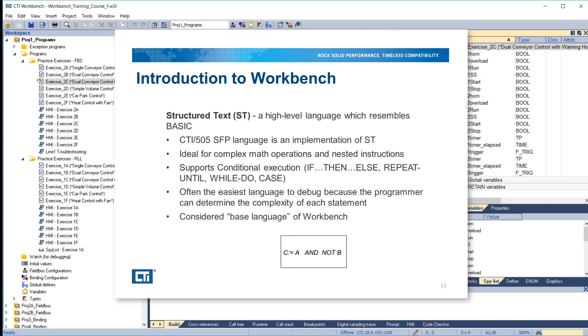Structured text is a high-level language which resembles BASIC. The special function programming language used in CTI and Simatic 505 CPUs is an implementation of structured text. It is ideal for complex math operations and nested instructions. It supports conditional execution using if-then-else, repeat-until, and while-do or case. It is often the easiest language to debug because the programmer can determine the complexity of each statement. Structured text is considered the base language of Workbench.